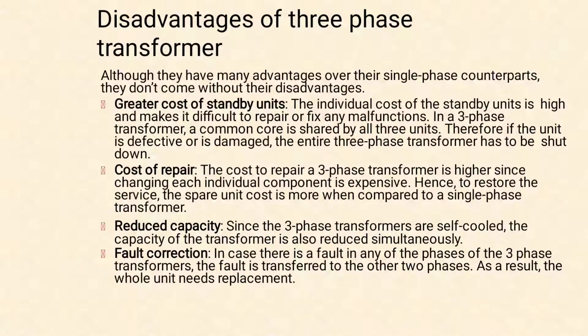Then what are the disadvantages of a three-phase transformer? Although there are many advantages, there are some disadvantages. One is the greater cost of standby units. The individual cost of the standby unit is high and makes it difficult to repair or fix any malfunction. In a three-phase transformer, a common core is shared by all three units. Therefore, if a unit is defective or damaged, the entire three-phase transformer has to be shut down. So it is not possible to shut down a particular phase. You have to shut down the entire device.